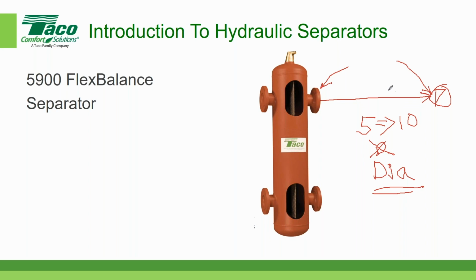However, the problem here comes in that the diameter of the hydraulic separator may not be the same pipe size as the pump, in which case that becomes a separate problem. Let's assume the hydraulic separator had a 10-inch connection and the suction side of the pump had 12 inches. I'm just making this up. Well, it would be the 12-inch that would be dictated in terms of the pipe diameter. So if you wanted to go at 5 pipe diameters, 5 times 12 would be 60 inches between these two. Hopefully that makes some sense.